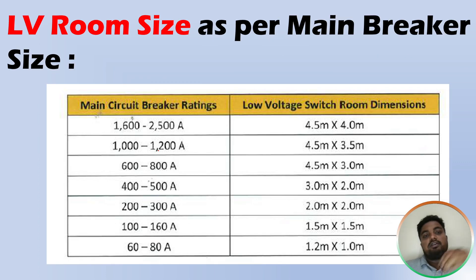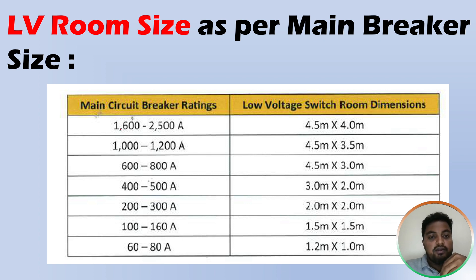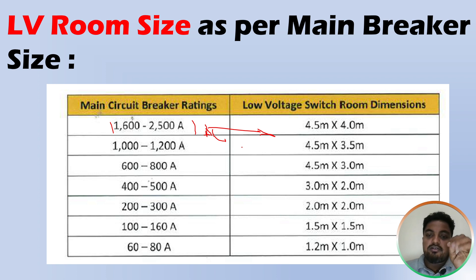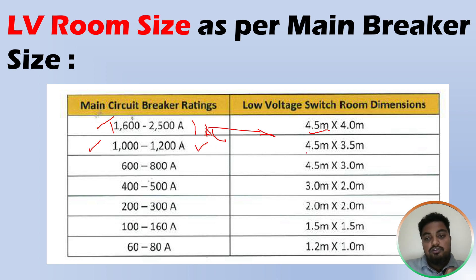Now we will see the LV room size as per the main breaker. This is applicable when you have one LV panel in the LV room. The first column is the main circuit breaker rating and the second column is the low-voltage switchroom dimensions. For a 1600A to 2500A ACB incoming, the minimum room size to allocate is 4.5m × 4m. For a 1000A to 1200A ACB incoming, the minimum room size is 4.5m × 3.5m.